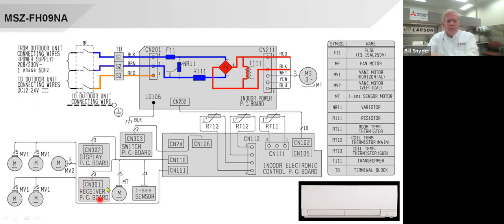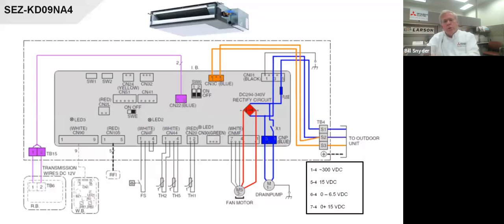And these are all just different boards: the receiver board for the remote controls, and the display board, which is the LEDs, that sort of thing. And then this I wanted to show you just because this SEZ is a little air handler. This is the indoor board for the air handler. Again, thermistors, works pretty much the same way, except for this one, instead of a remote control, you actually have a wired control. This one happens to be what they call a simple MA. And there's just two wires that connect onto the control board. There's just a terminal board here that you would wire your thermostat wire to on this one.